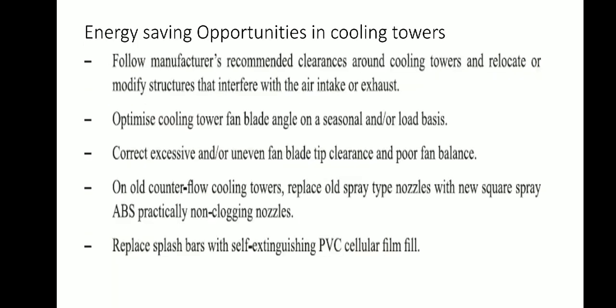Then the energy saving opportunities in cooling tower. Follow manufacturer recommended clearance around cooling towers and relocate or modify structures that interfere with the air intake or exhaust. Optimize cooling tower fan blade angle on seasonal and or load basis. Correct excessive and or uneven fan blade tip clearance and poor fan balance.